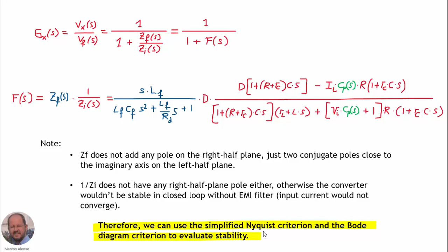Now it's important to note the following. First, ZF does not add any pole on the right half plane, as we have seen, just two conjugate poles close to the imaginary axis, but on the left half plane. And also 1 over Zi does not have any pole on the right half plane either, because otherwise the converter wouldn't be stable in closed loop without the EMI filter. In that case, the input current would not converge, and we have seen that the converter is stable without the EMI filter. So why is this important? This is important because therefore we can use the simplified Nyquist criterion and the Bode diagram criterion to evaluate the stability of the system. And now let's analyze the first example.